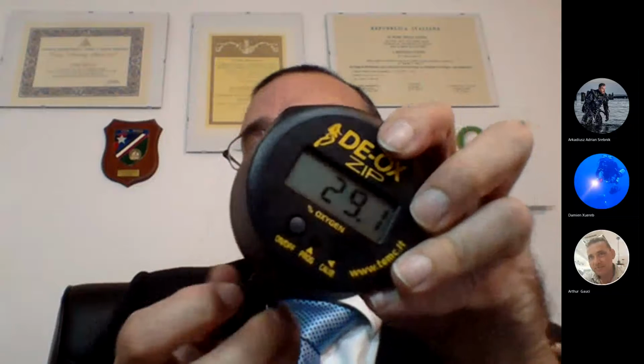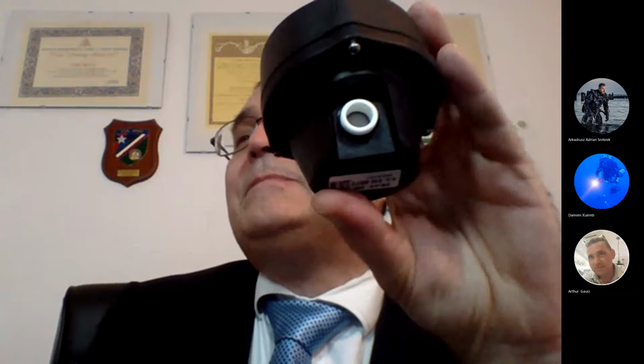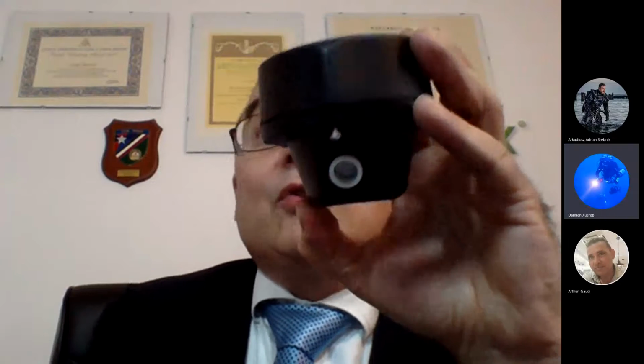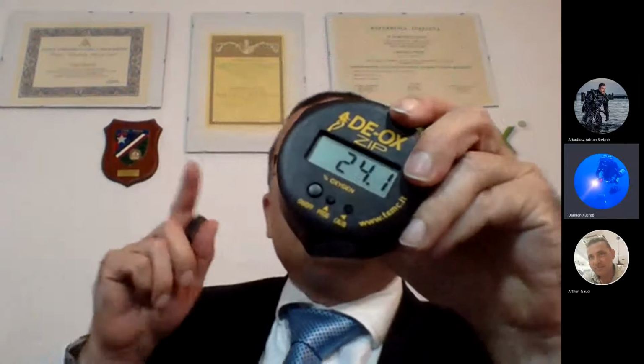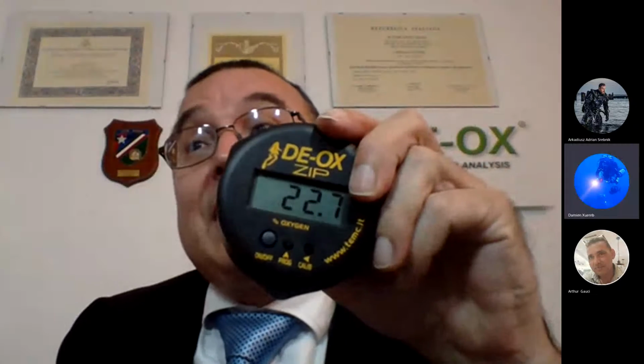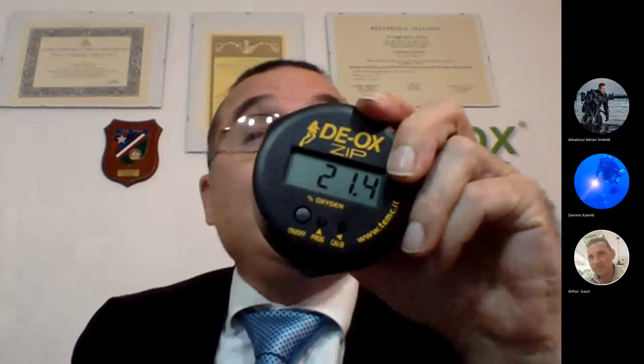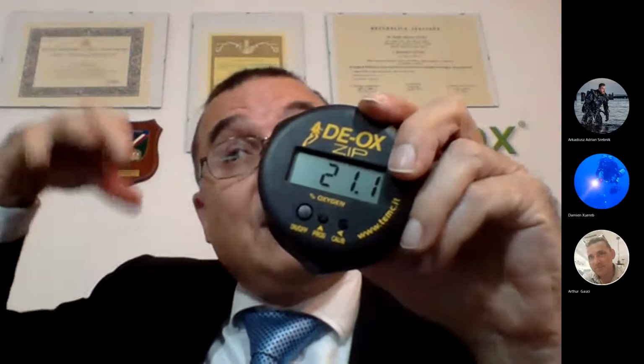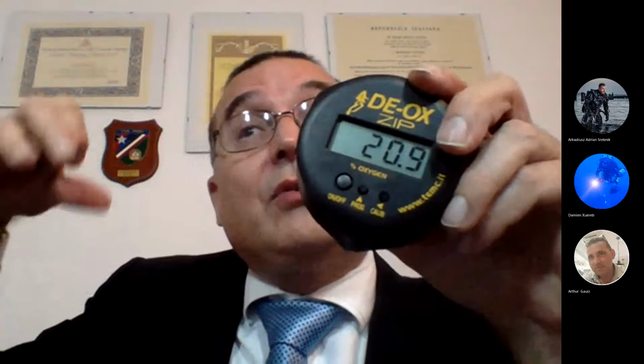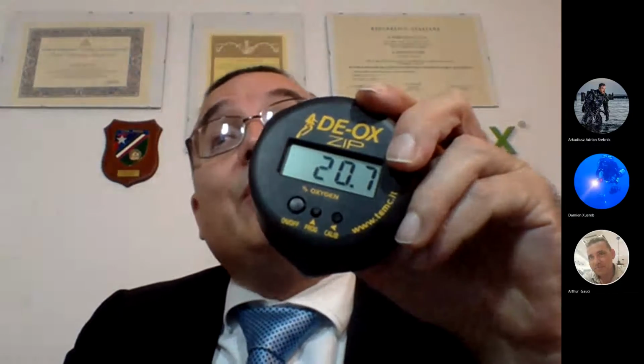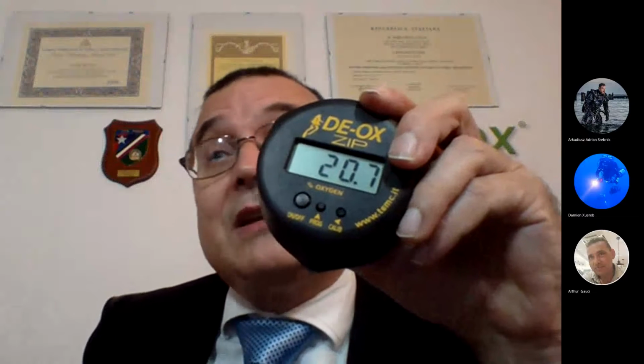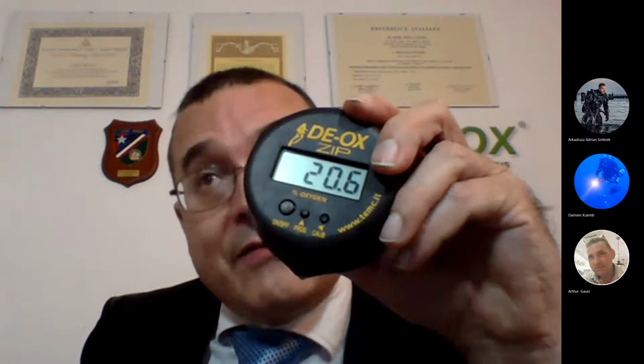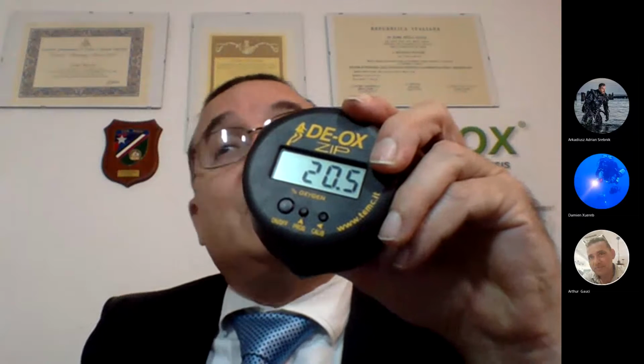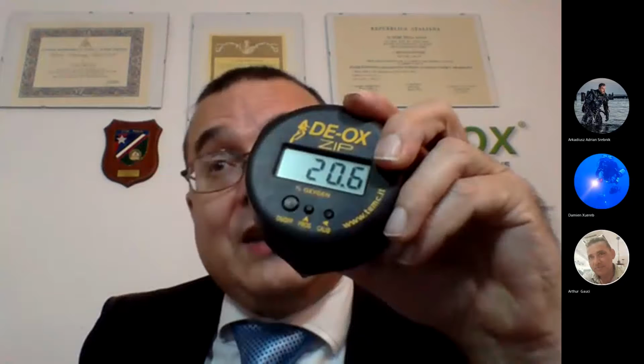I can remove the adapter. And then also, guys, don't underestimate when you use pure oxygen in a closed area like my office here, even if it's quite big, you have an increase of oxygen in the room, so you don't have the ambient at 21%. Maybe you have 21.5, 21.6 very easily, even if you use a very, very low bar of pure oxygen. The ambient oxygen will change, so don't use that air for doing the calibration.